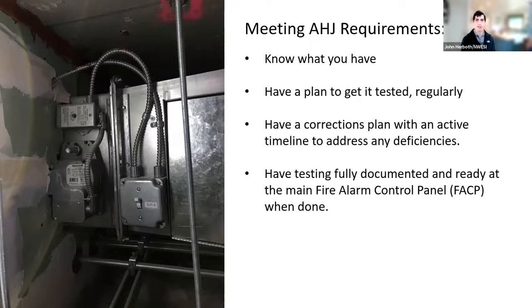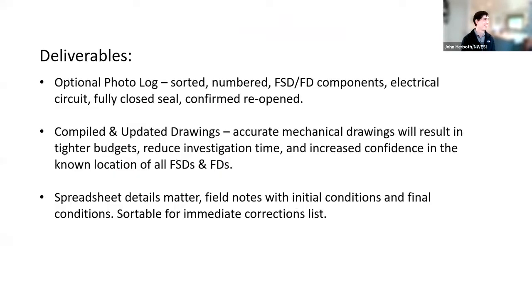We all know documentation of existing buildings is sometimes a layout drawing at best, or an evacuation layout drawing. But here are some options, just real quick. You could do a photo log for critical environments where you know how you left the component. You could take a picture of it as you found it, or closed as you tested it, and then a second picture of it open and returned to operation. So when you leave that damper, especially at a hospital, you know that you left it in an operating condition in the open position, if that's the normally open position for fail-safe.